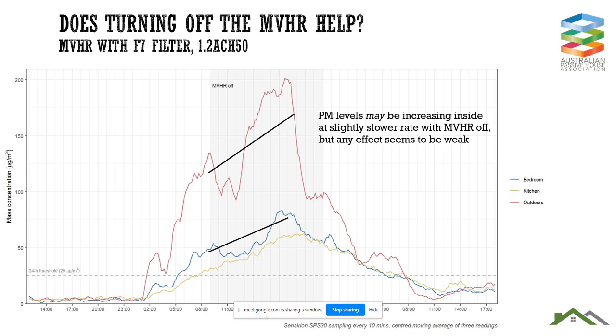And of course it comes with consequences in terms of indoor air quality. I think that by the end of this day, with 3 occupants, we were up to about 1,500 parts per million CO2, so that wasn't going to be an acceptable long-term solution to these sorts of events.